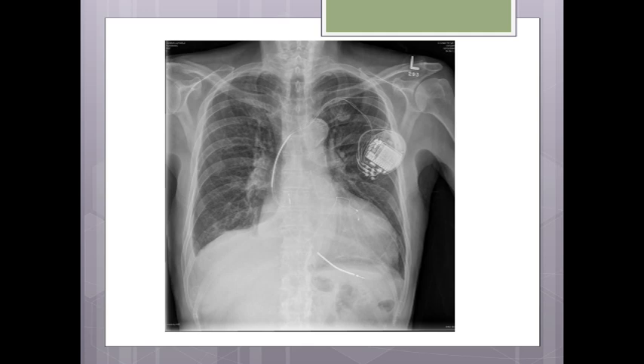An example ICD is shown implanted with a thick radio-opaque coil at the SVC–right atrium junction and another at the right ventricle — these are the shocking coils. Two coils allow shocking in multiple directions: atrium only, atrium to generator casing, ventricle to generator casing, or between the two coils.